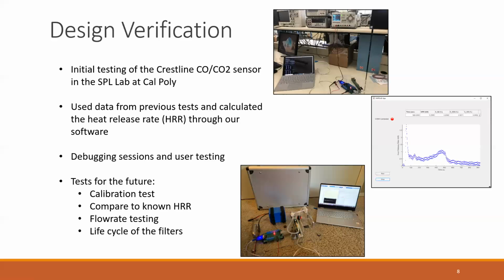And we also would like to compare to a known heat release rate. So we would actually burn a substance in the fume hood, measure it, and compare it with the calorimeter and the known value. But unfortunately, we can't do that now. Also, we need to do flow rate testing and the life cycle of the filters to ensure that the system is running properly and that it can run properly in the future.